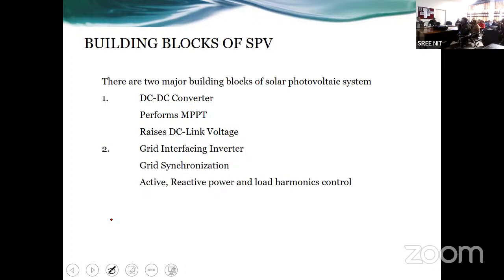So this was the concept: active power, reactive power, and load harmonics can also be supplied by the grid interfacing inverter simultaneously. Because most of the time, let us say you have 10 kilowatt solar power generation and a 10 kilowatt inverter, but most of the time you are generating only 20 or 30% of your nameplate capacity, or 60% of your capacity. So the rest of the power electronics capacity is still available in the inverter. For that remaining capacity, I would like to keep supplying the reactive power demand or the load harmonics of a nearby load.